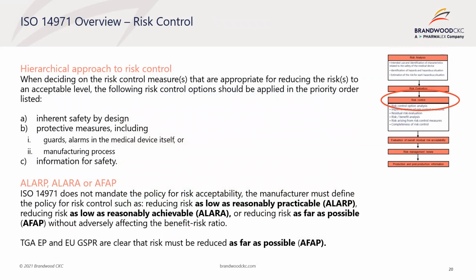When deciding on the risk control measures that are appropriate for reducing the risks to an acceptable level, the following risk control options should be applied in the priority order listed. Firstly, introducing safety by design, by eliminating a particular hazard, or by reducing the probability of occurrence of the harm, or by reducing the severity of the harm. Adding protective measures, including preventing the occurrence of a hazardous situation using, for example, a guard, preventing a hazardous situation from leading to harm, using, for example, alarms in a medical device itself or in the manufacturing process, adding information for safety within the product labeling.